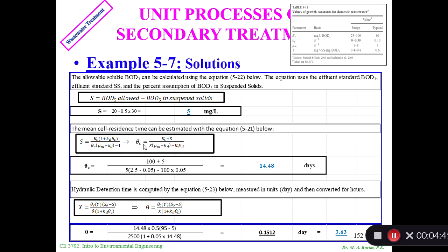We'll be using the Excel spreadsheet. I input the data already. S using equation 5-22: S equals BOD5 allowed minus BOD5 in the suspended solid. S equals 20 minus 50% of the suspended materials. The suspended materials allowed is 30, so I got 5.